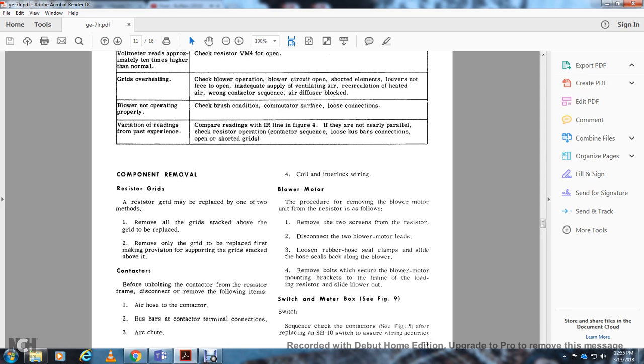Component removal, resistor grid. The resistor grid may be replaced by one of two methods: remove all the grids attached above the grid that will be replaced, or remove only the grid to be replaced, making provisions to support the grids stacked above the contactors. Before unbolting the contactor from the resistor frame, disconnect and remove the following items: 1 air hose, 2 contactor bus bar with the contactor terminal connections, 3 air chute, 4 coil and interlock wiring. Blower motor: the procedure for removing the blower motor unit from the resistor is as follows.